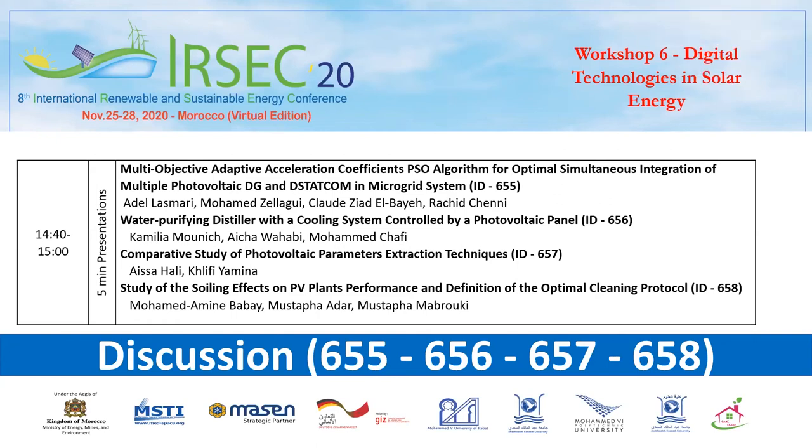Ground measurements, and we used the first PV grid-connected plant based on monocrystalline silicon PV modules of Sunmodule Plus from Solarworld. The modules are connected in series making a peak power of 2 kilowatts injected to the grid through an SMA 2000 inverter. The second installation is based on polycrystalline silicon PV modules, and the third PV plant consists of 12 silicon modules of the brand Next Power, with an output of 155 watts per module. We have three families: monocrystalline, polycrystalline, and amorphous. Three technologies.